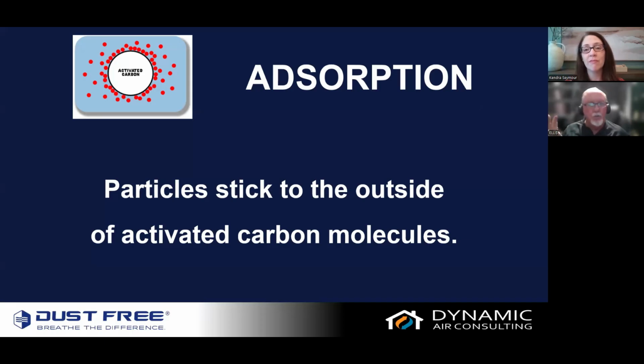You'll hear me say 'truly activated carbon' because there's a misconception in the marketplace—when people see a carbon filter in big box stores or even supply houses, it's often not truly activated carbon. It is carbon by default; we're all carbon by default if you want to look at it that way. But most impregnated filters use granulated charcoal, which is carbon, in such a small amount because air still needs to pass through the filter. So any adsorption properties are short-lived, depending on time of use, and humidity really beats up carbon. Since it's granulated, there's not a lot of mass in each granule when we impregnate a filter. That has been a big misconception in our marketplace.